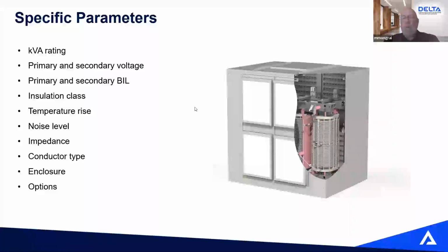Do I go with copper? Do I go with aluminum? What type of enclosure am I going to use if I replace the enclosure? Is there a sprinkler in the room? Do I need a sprinkler-proof enclosure? What kinds of options? Do I need cooling fans? Do I need a temperature controller? So there's lots of questions to go through and ask ourselves when we replace a transformer.